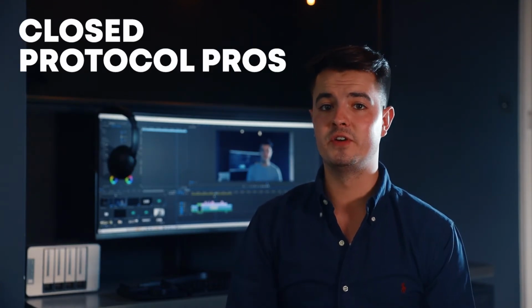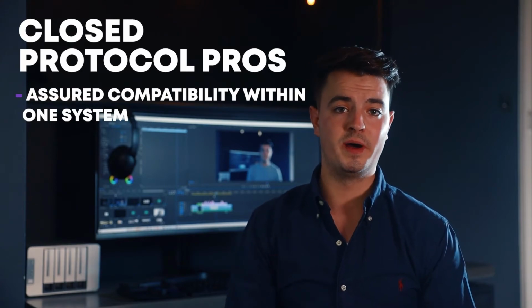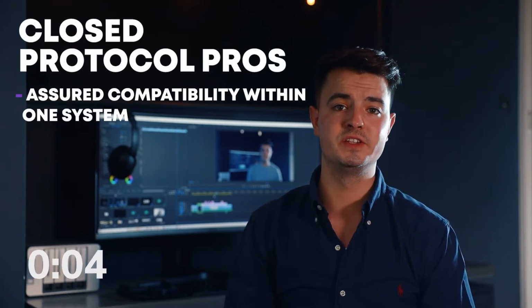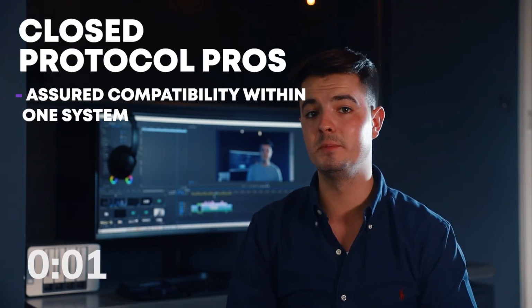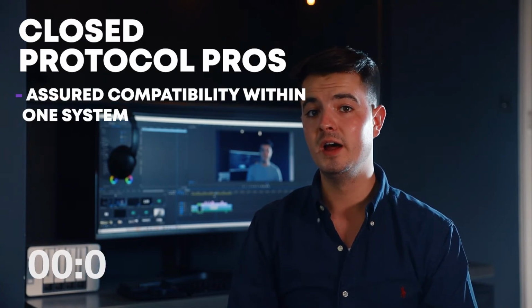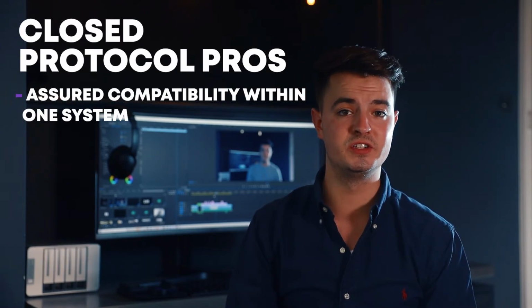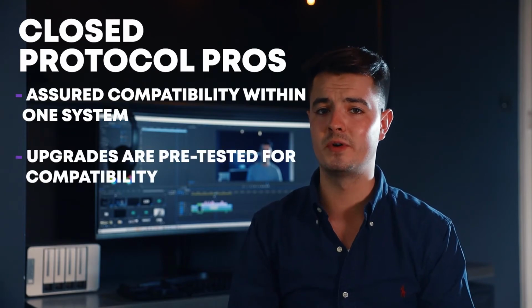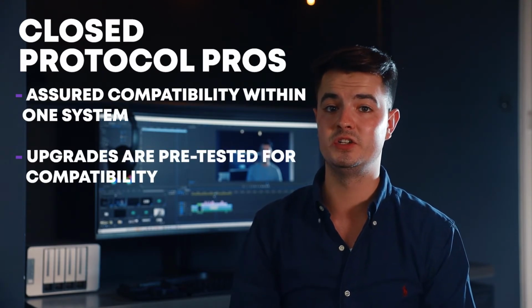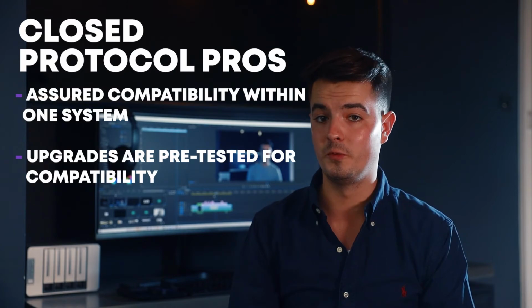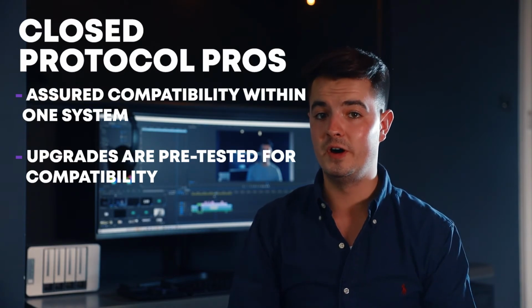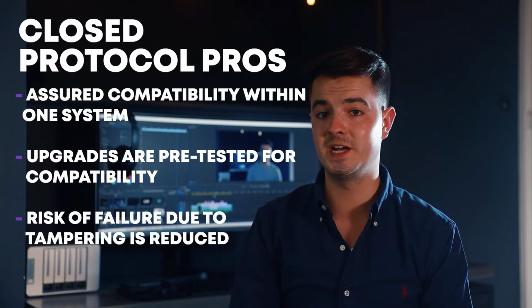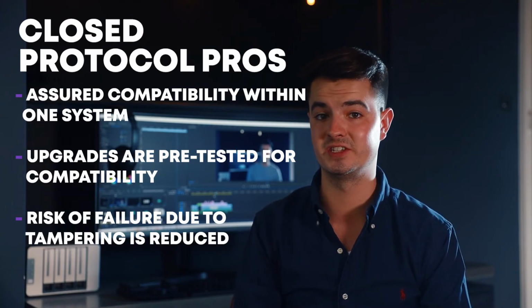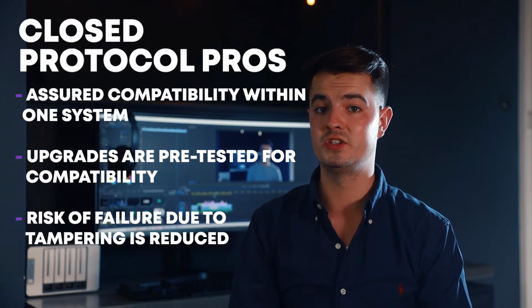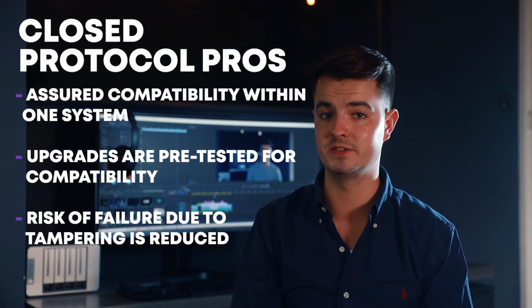Firstly, because each and every device in the system, including the control panel, is provided by one manufacturer, there's a common design and production plan, meaning compatibility is assured. Secondly, when individual devices do need upgrading, they're tested alongside the rest of the manufacturer's product range to ensure the system's compatibility before the products are brought to market. Finally, system failure due to unauthorised tampering is reduced as access to the system is restricted by the manufacturer to approved installation and maintenance companies.